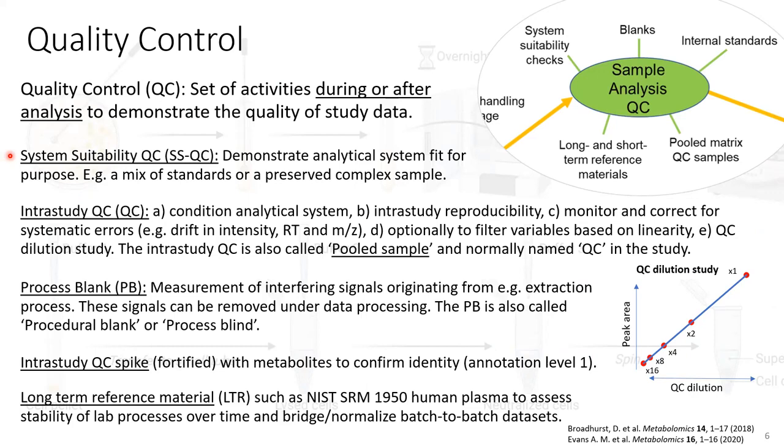And what we typically do in our lab is that we have a standard that has been spiked into a matrix with at least 50 different components, metabolites or pharmaceuticals, and then we run that on the platform, and then we check if the retention times are good enough, the mass accuracy is good enough, and so on, the intensity of the samples, intensity of the metabolites, and if it's good enough, then this platform is okay to use.